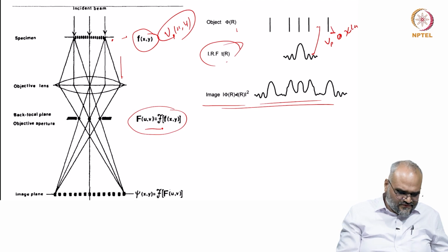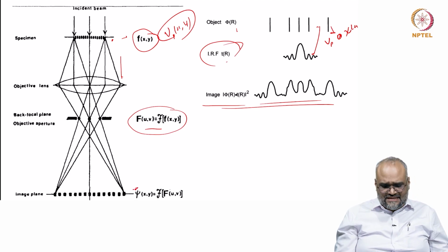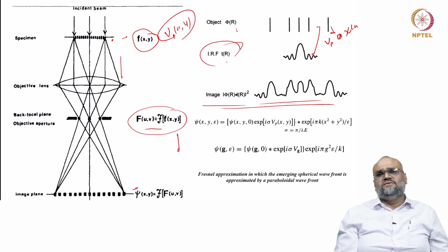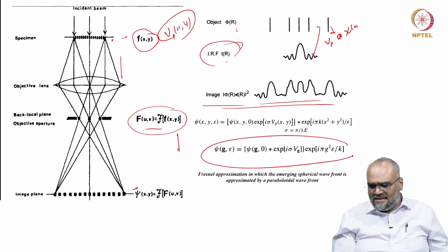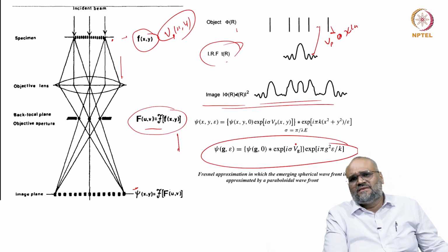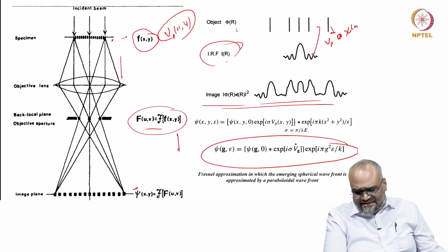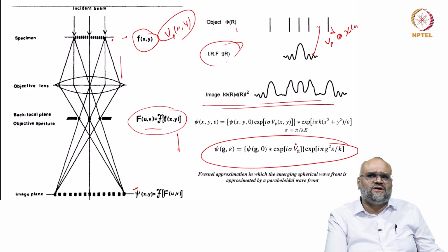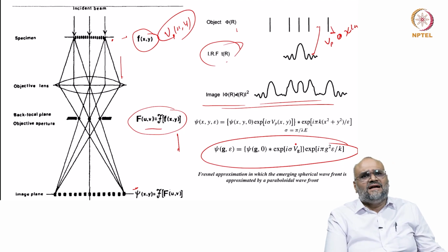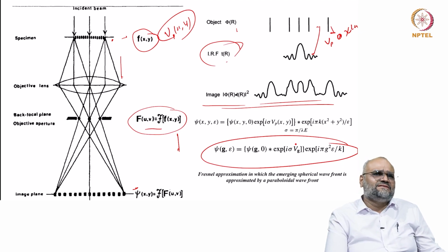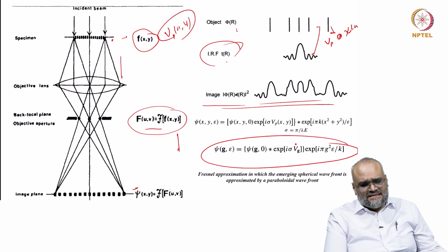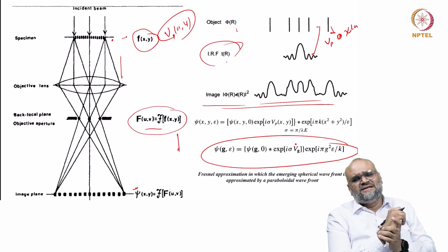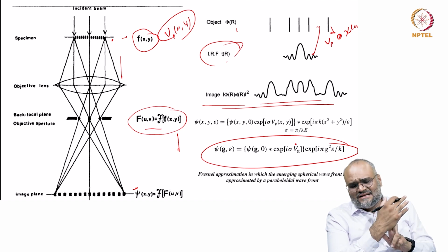and what I record at the image plane is again an inverse Fourier transform of this. So, from all these you can summarize the information you record for an exit wave is given by a function like this, which is strongly dependent on the thickness, the defocus and the lens aberrations. And by minimizing the spherical aberration and chromatic aberrations, your aberration corrector actually breaks the resolution barrier. This is imaging by looking at parallel illumination, whether it is bright field, dark field or high resolution imaging.